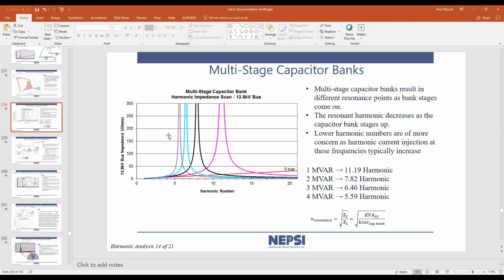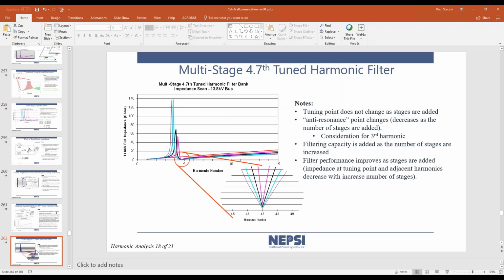So the question is what do I tune that filter system to? And really, that's unrelated to the number of stages on. Generally, what is done is that it is always the 4.7th or somewhere around the 4.7th. Some people are going to tune at 4.0, 4.1, 4.7, 4.8, and some will tune at 4.9. But generally, you're going to tune a capacitor bank to be somewhere beneath the 5th harmonic.